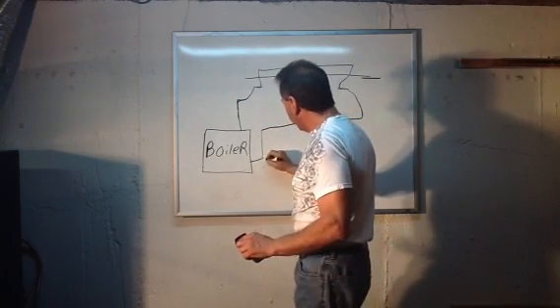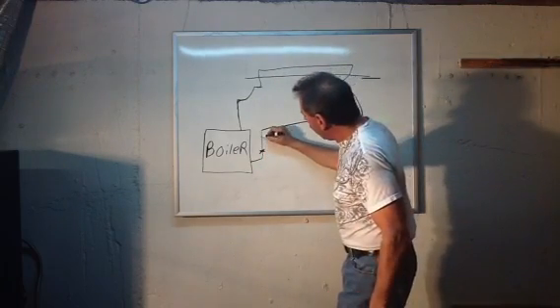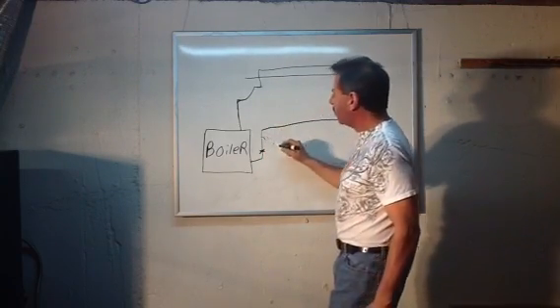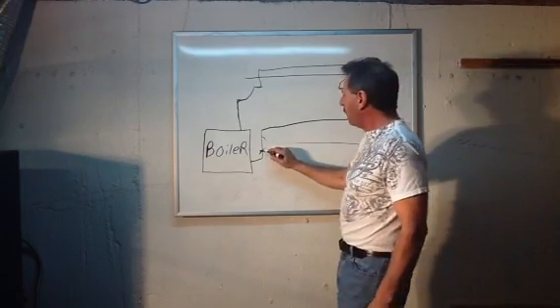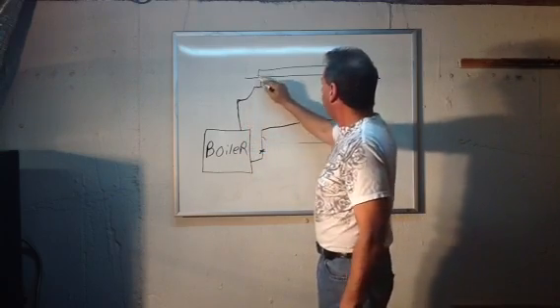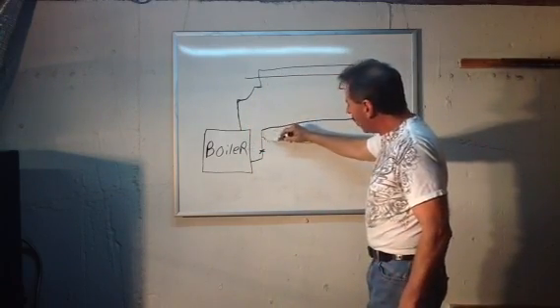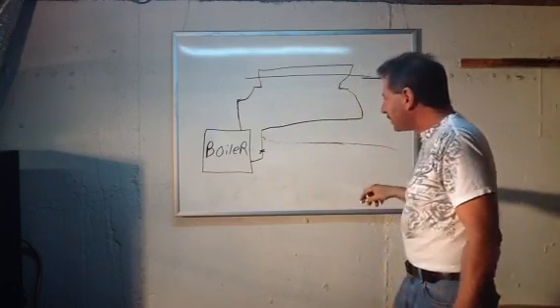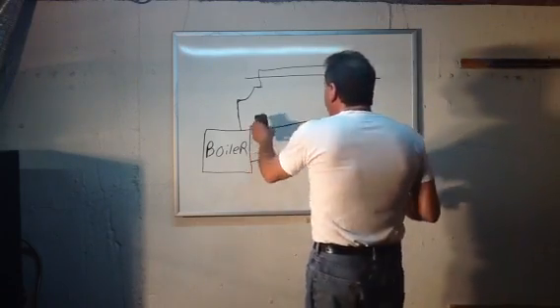At one point when you do the baseboard, on the way down to the boiler, there has to be a valve that shuts the water flow off and a garden hose bib where you can screw a hose on, put it out a window. You have to shut the one valve and open the other to force the hot water up and push all the air out. The air will come out that garden hose and you run that for about 10 minutes.